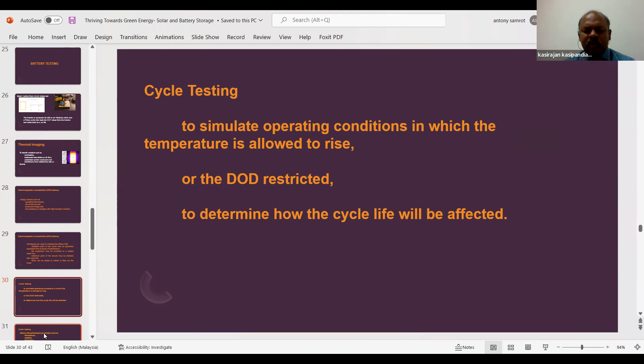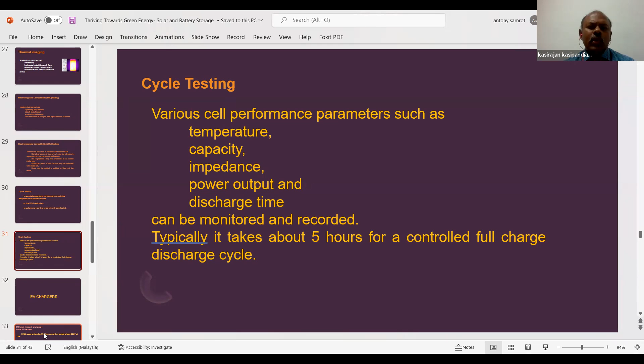What are the different parameters? Temperature, capacity of the battery, impedance, power output, and discharge rate. These can be continuously monitored and recorded. It takes 5 hours for a controlled, fully charged discharge cycle for the cycle test. These are the different tests we need to do for batteries before submitting to the government for approval.